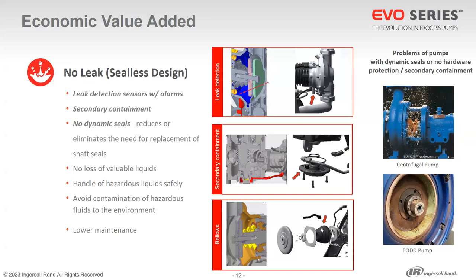I want to emphasize some very popular problems with pumps that don't have this type of protection or secondary containment. Two examples: popular existing centrifugal pumps that experience a lot of leakage or escapes, and another example of an electric double diaphragm pump — even if it has some leak detection, it's very clear that leakage escaped and started to damage all the internal hardware of the system.